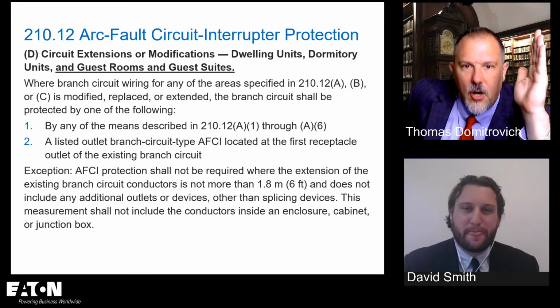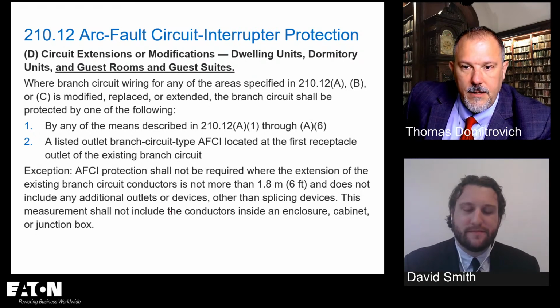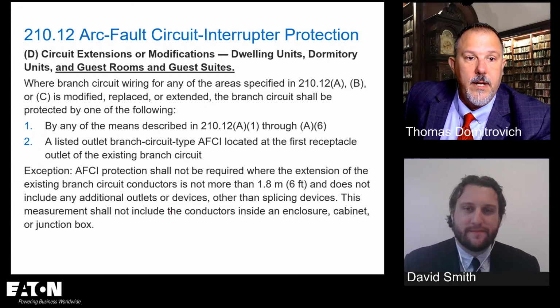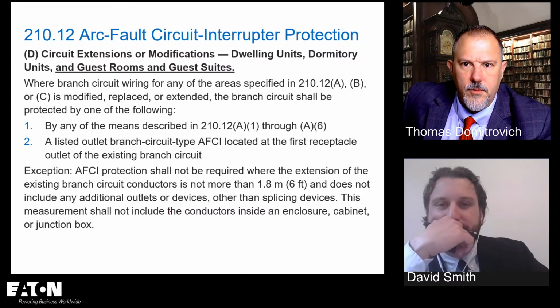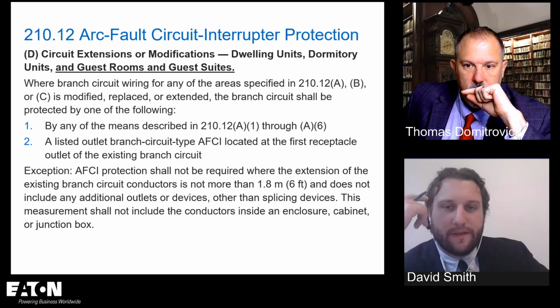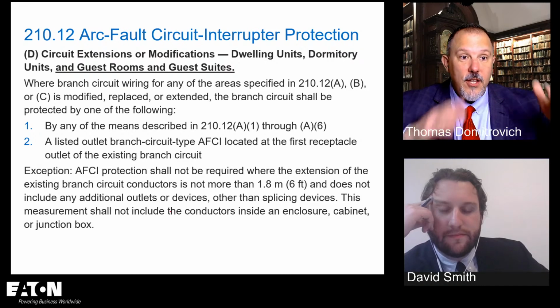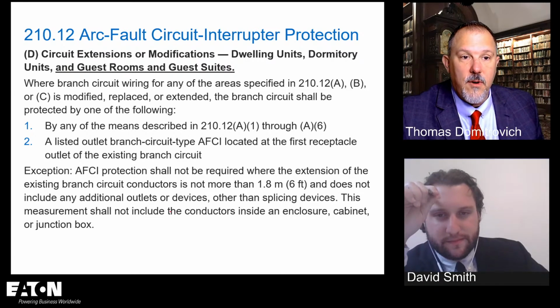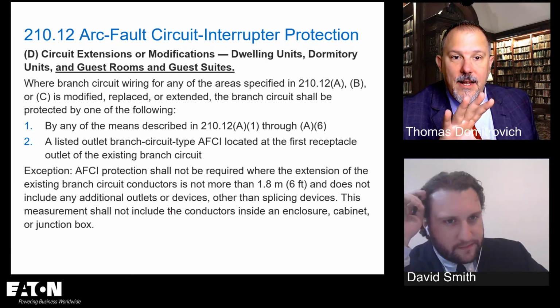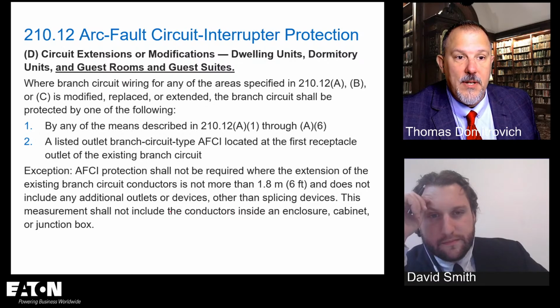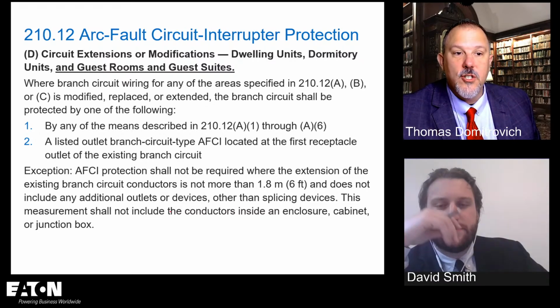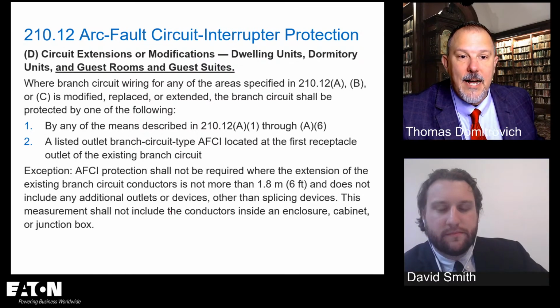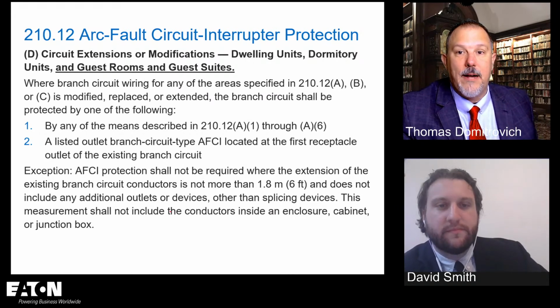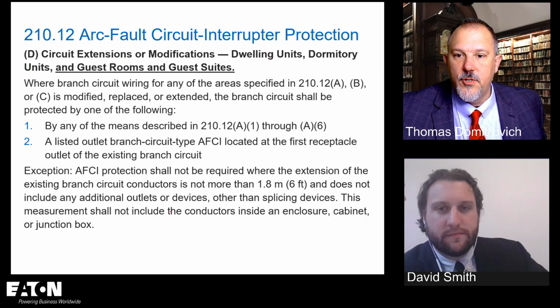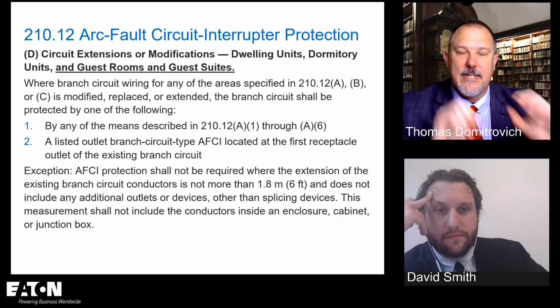When you look at all of the arguments on AFCIs, even the home builders will say the problem is not with new homes. The problem is with existing homes. Now, you've got 210.12(D), circuit extensions or modifications. Where branch circuit wiring for any of the areas specified in 210.12 (A), (B), or (C) is modified, replaced, or extended, the branch circuit shall be protected by one of the following, by any of the means in (A)(1) through (6), so there's 6 options. A listed outlet branch circuit AFCI located at the first receptacle outlet. So we're saying, okay, I'm not going to worry about the home run circuit for an existing home. We just want it in existing homes.